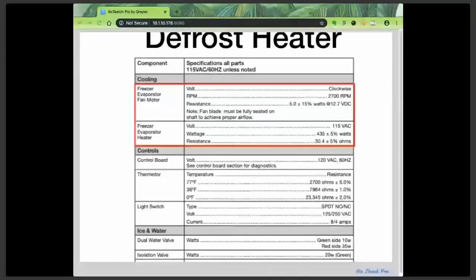So you'd force defrost on the unit by whatever key dance is on that particular control board, then clamp your amp clamp around the wire going to the load of interest and see if it's in the expected range. And how would we do that?